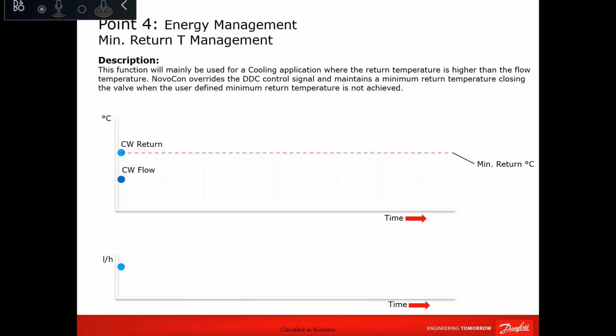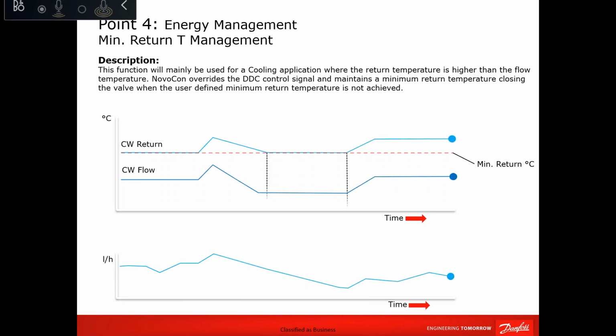Another feature is the minimum return temperature, because as you know, when you try to control delta T, what is the downside? The supply temperature might increase, and in some areas you might see some discomfort. If you have doubt on how suitable your supply chilled water temperature is, whether it is low enough or high, you can just set the return chilled water temperature. Let's say, regardless of what I am having, I would just set the return temperature to 14.4 to achieve the district cooling requirement and not have any surcharges. So in this case, the Novocon will adjust itself to maintain that return temperature only.